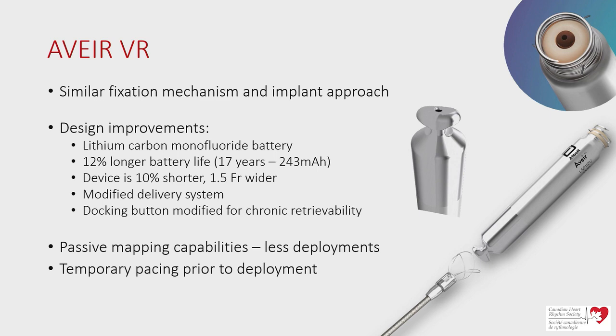The interesting thing about this device over the Micra is that you're capable of passive mapping. So you can look at your electrical parameters, sensing and threshold and impedance prior to deploying. And you can also temporarily pace through the device prior to deployment. So if you create a couple PVCs on your way in and knock out the escape rhythm, or knock the right bundle in a left bundle patient, then you've got some means to support the patient while the implant occurs.